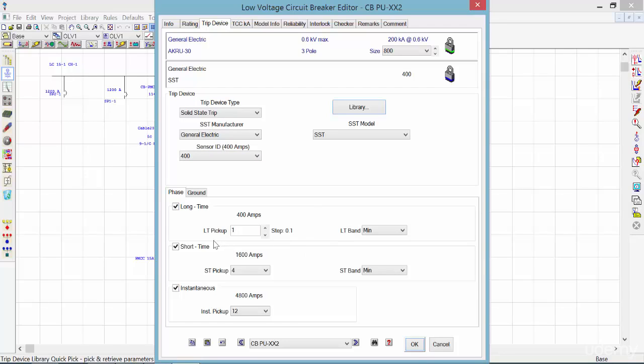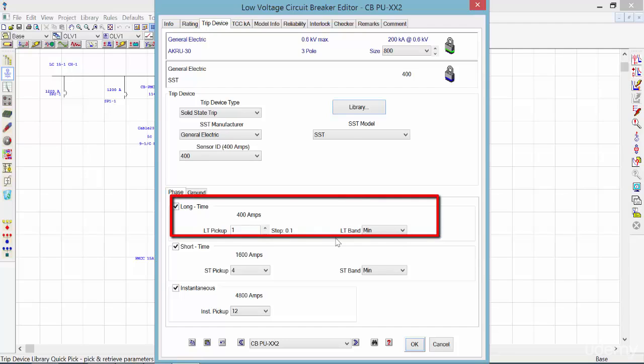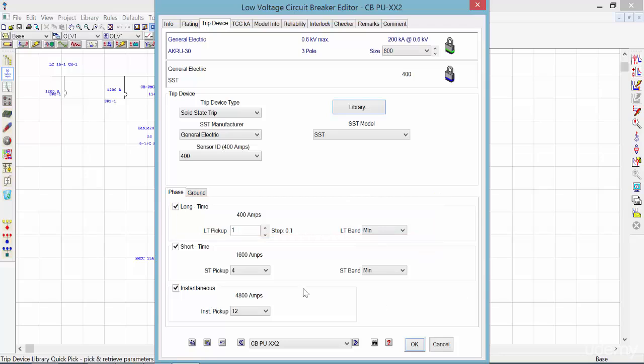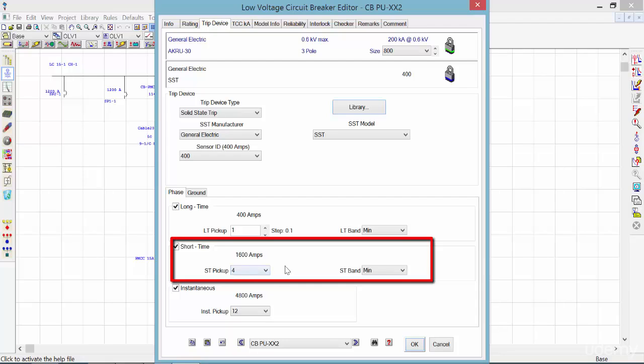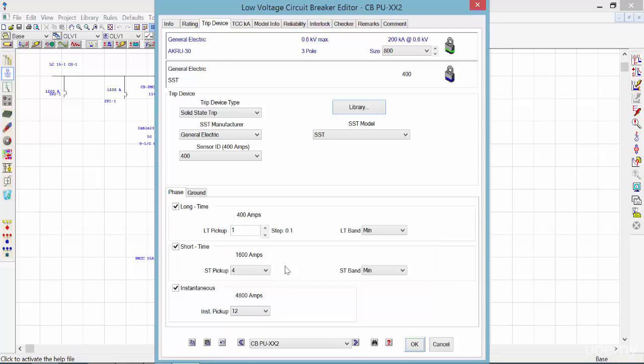Each phase, the LT pickup or long time pickup, is when the breaker picks up, and it's set at 400 amps, and the band is set to a minimum for the accuracy. The short time pickup is 4 times the full trip of the circuit breaker, which is 4 times 400, and it's 1600 amps. And it's also set to minimum. The instantaneous amount of fault current that this breaker can handle is set to 12 times its rated amp, which is 4800 amps.